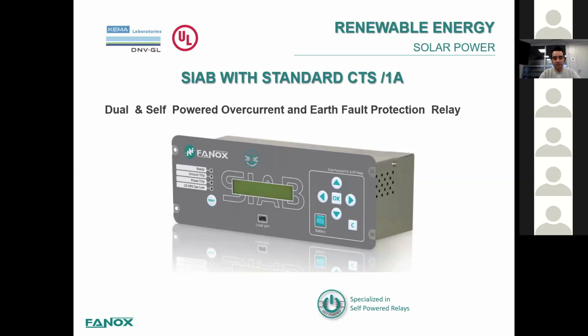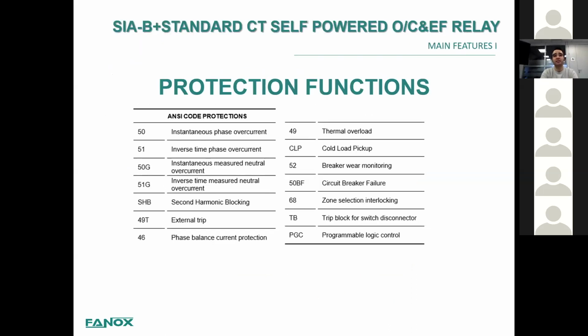This is a SIA-B that works with the standard CTs. The main difference, as you can see on the layout, is a very compact relay, and it has not only the traditional overcurrent and earth fault protections, but again, second harmonic blocking, cold load pickup, monitoring of the circuit breaker failure, trip block, switch disconnector, and it's also possible to have a zoning selection interlocking with the inputs, outputs, and communications.